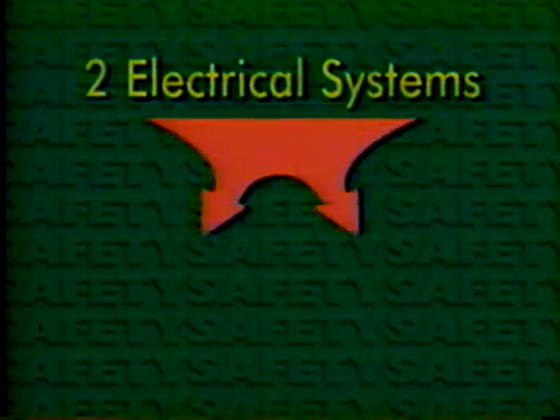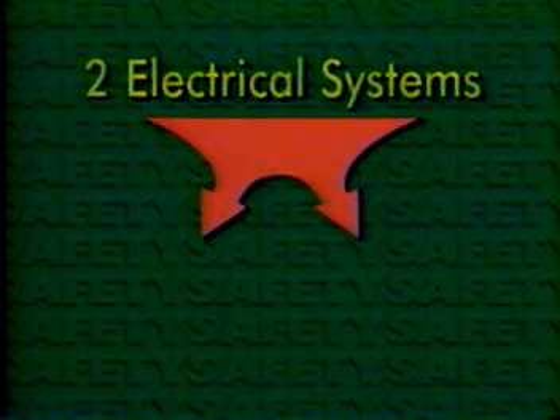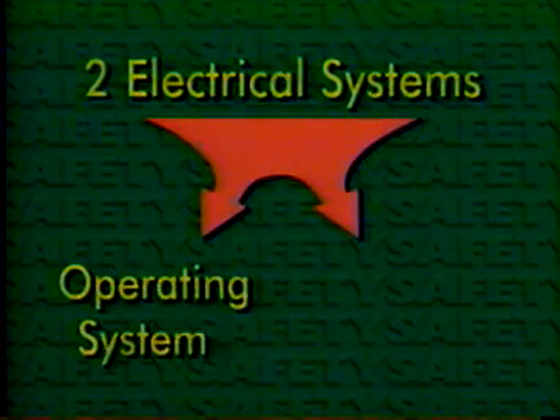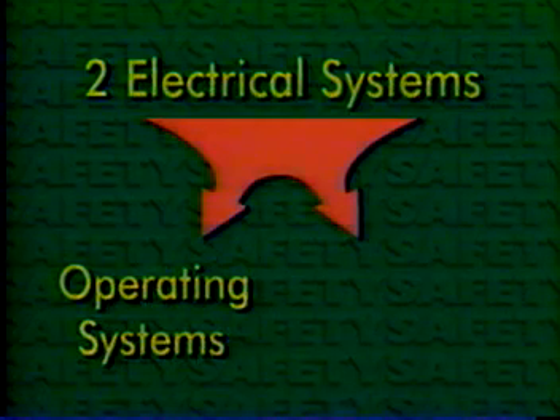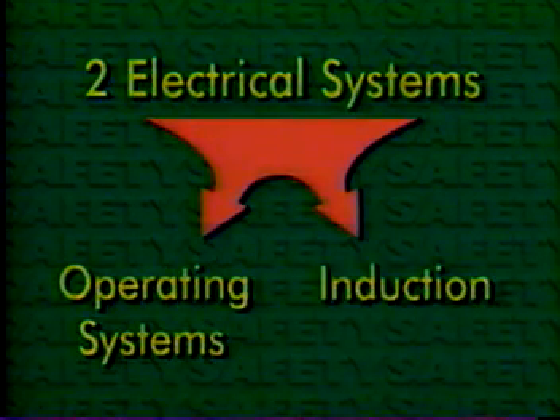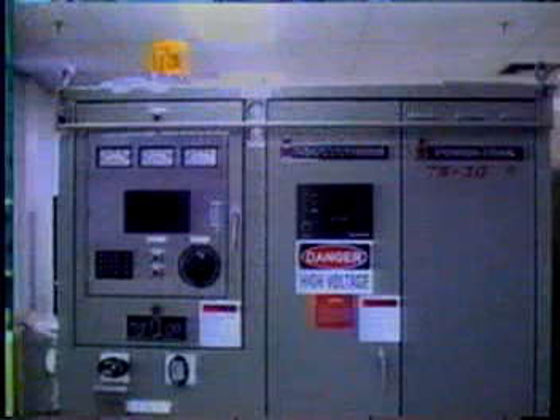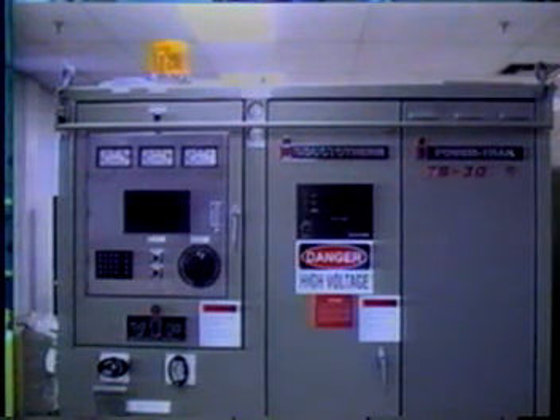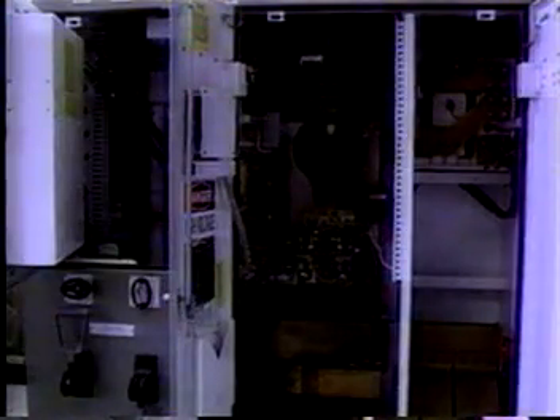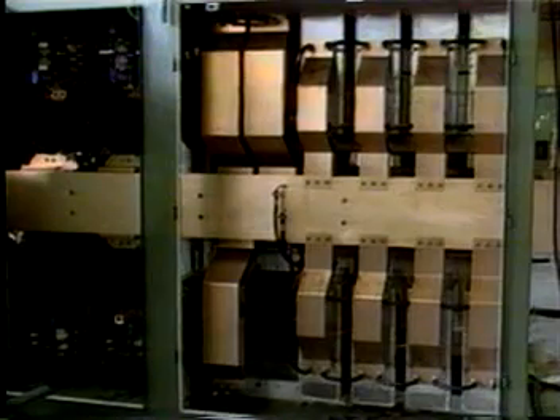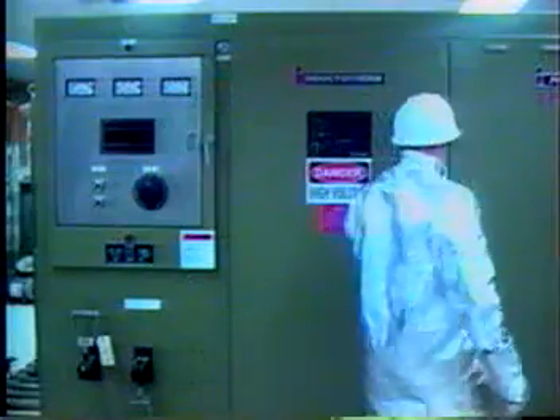Typically, induction furnaces require two separate electrical systems. One for the operating system, such as the cooling system, furnace tilting, and instrumentation, and the other for the induction coil power. Electricity for the induction coils normally is furnished by a specially designed power supply connected to a three-phase, high-voltage, high-amperage utility line. This means that foundry workers cannot assume that the power to the furnace coil has stopped just because service has been interrupted to the furnace's cooling system or hydraulic pumps.